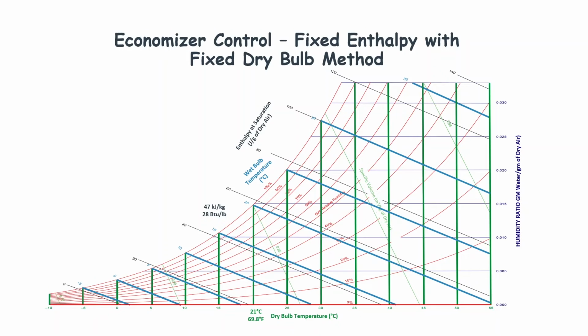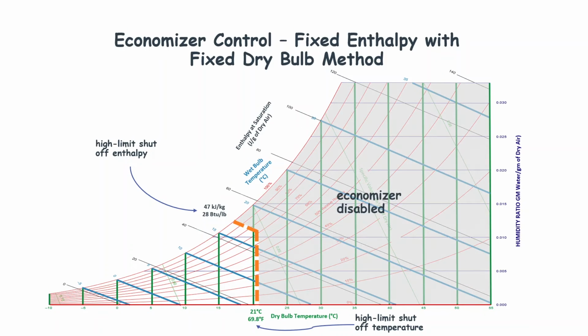The third control method is fixed enthalpy with fixed dry bulb. In this method, the controller compares the outside air's enthalpy and dry bulb temperature with programmed high limit shutoff values. The controller disables the economizer when the outside air's enthalpy is above the high limit enthalpy, or it disables the economizer when the outside air's dry bulb temperature is above the dry bulb's high limit.